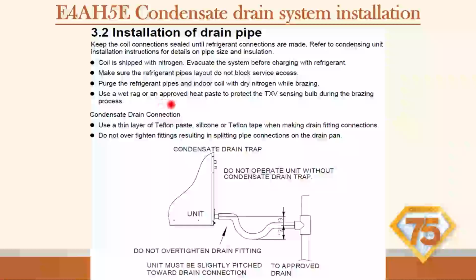Use a wet rag or approved heat paste to protect the TXV sensing bulb during the brazing process. I always just remove the whole bulb off of there. You undo the insulation, you undo the strap and take it away from there. Just eliminate any kind of concern that you're going to overheat that bulb.